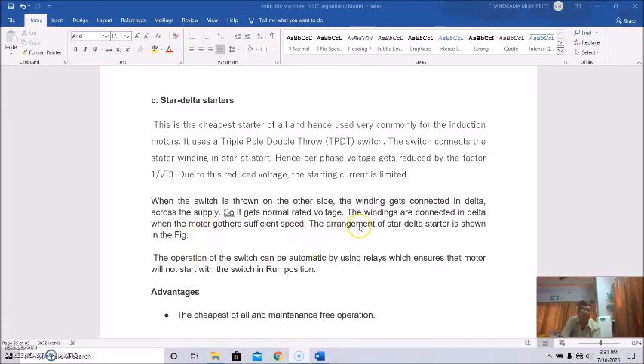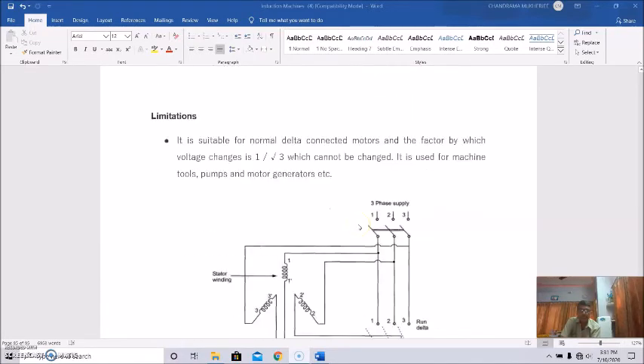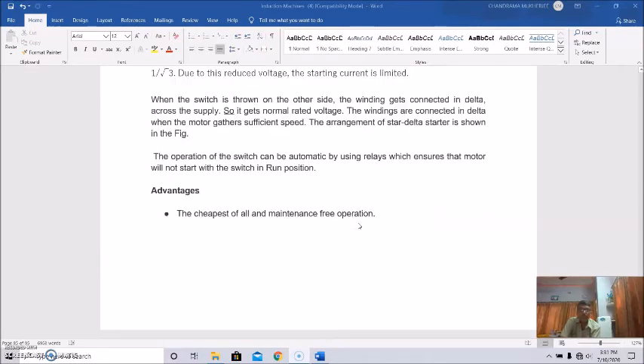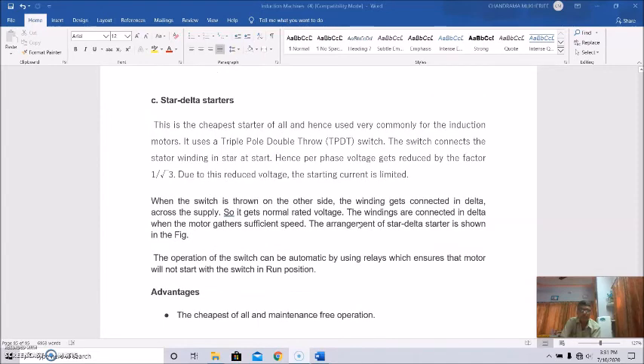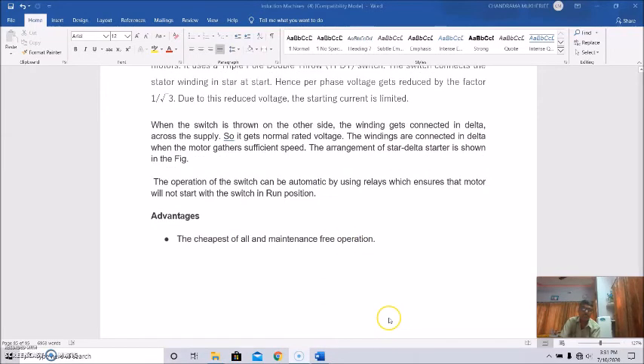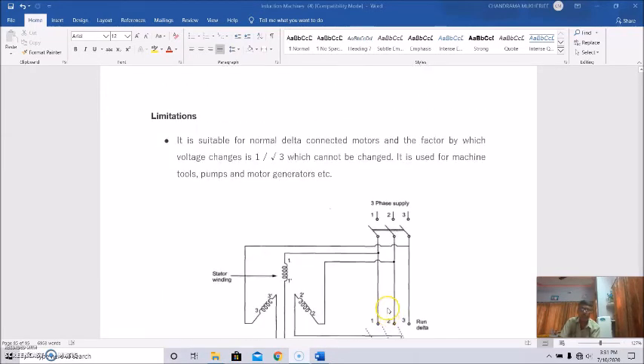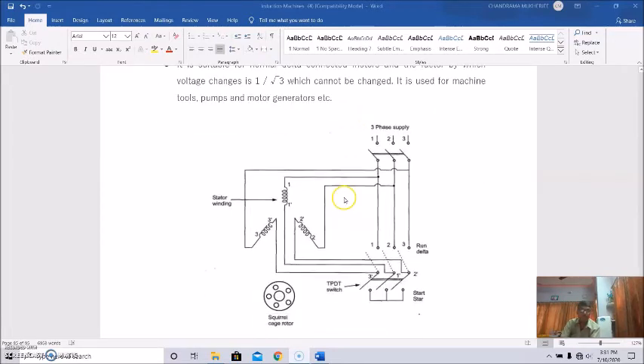And the arrangement of the starter is also shown here. The advantage of this type of starter is that it is the cheapest of all types of starters, and maintenance free operation is possible. But the limitation is that it is suitable only for delta connected motors, and the factor by which voltage changes is 1 by root 3, which cannot be changed. So it is used for machine tools, pumps, motor generators, etc.